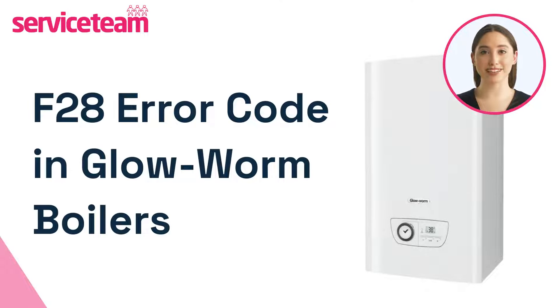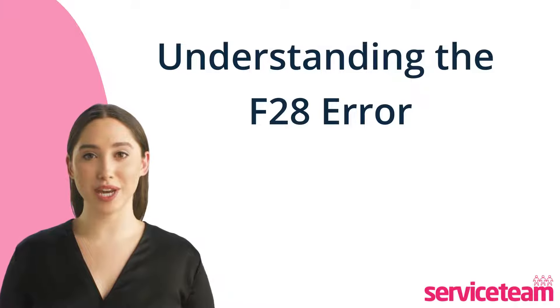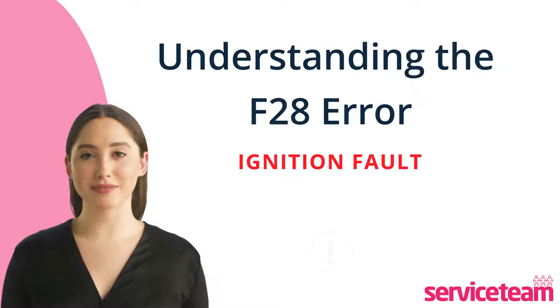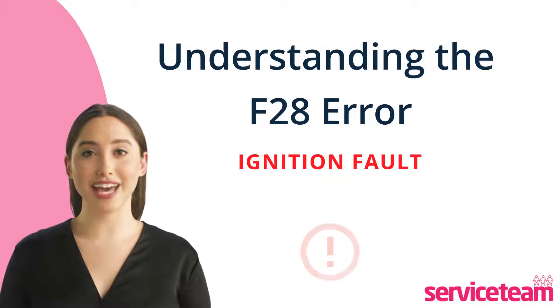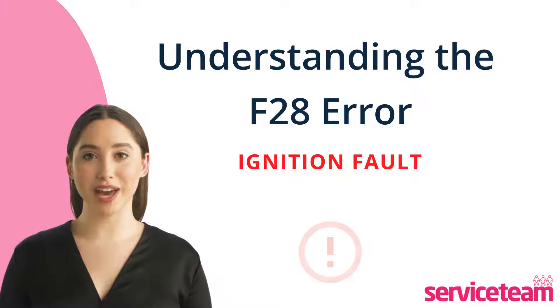If your Glow-Worm boiler has an F28 fault, we're going to discuss how to fix this error code and get your boiler back up and running smoothly. The F28 fault with Glow-Worm boilers typically signals an ignition issue, which could be caused by various factors such as a lack of gas supply or a malfunctioning part like the gas valve.